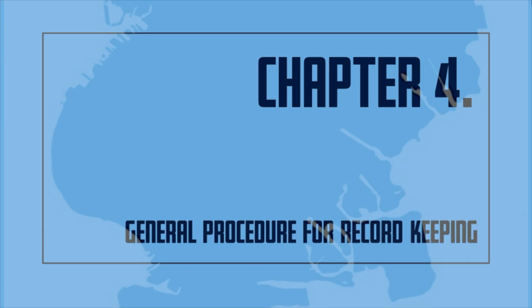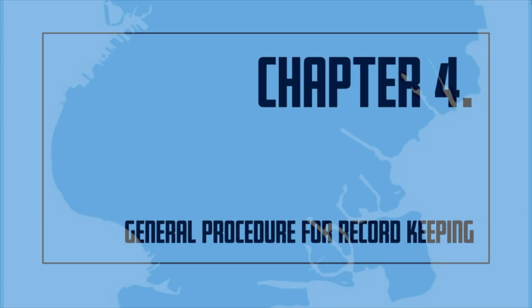Chapter 4. General Procedure for Record Keeping, Impairments, and Safety. It shall be the responsibility of the certificate of fitness holder to perform the following. Record keeping. The certificate of fitness holder shall maintain a detailed record of all inspections. A record with the date of each inspection, the certificate of fitness number, and the signature of the certificate of fitness holder shall be posted near the main control valve.